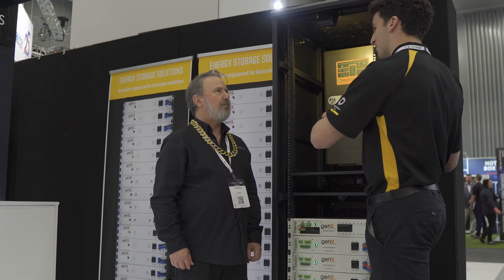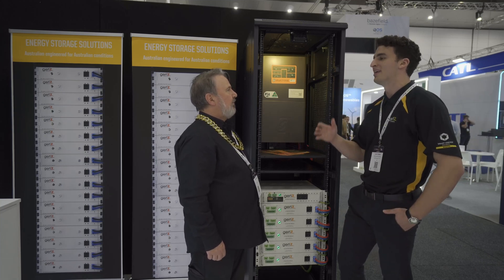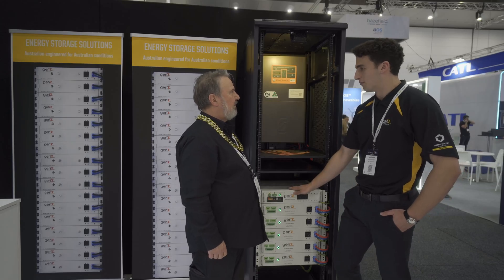There's a reason there's two of them — so you can parallel multiple racks. And if you've got a full set of 21, then you need the two outputs to have a low resistance output. So with this distribution module, how many battery modules can we connect? With this one here, it's a 21-port distribution module, so that's a full 21 batteries.